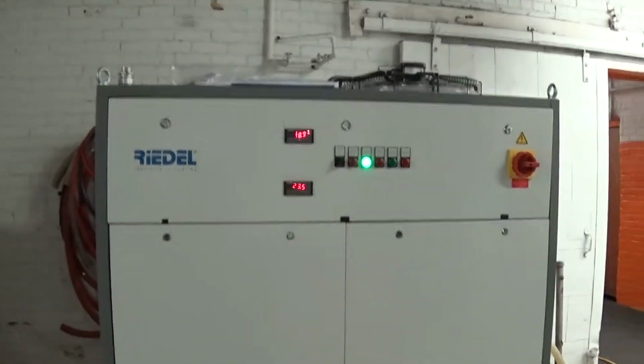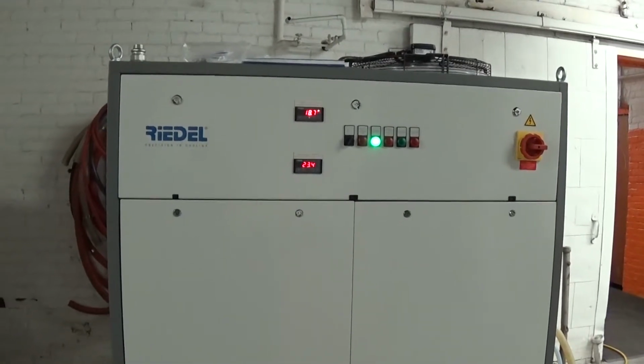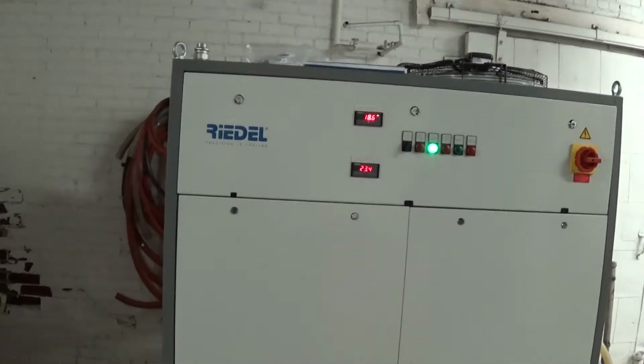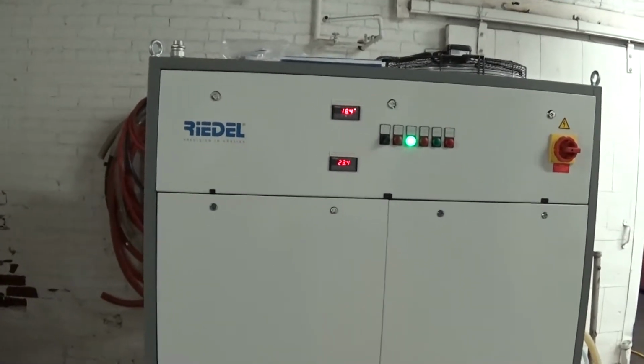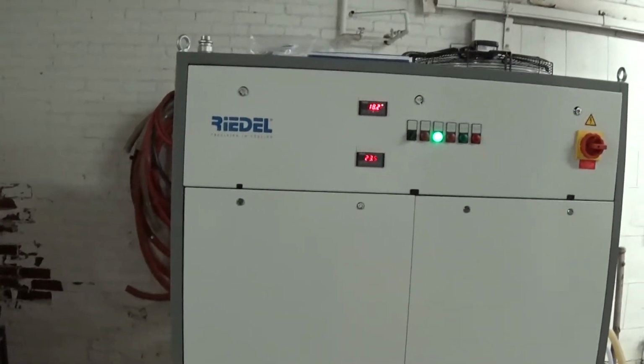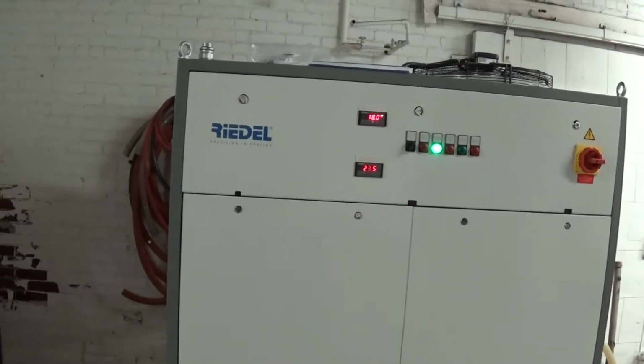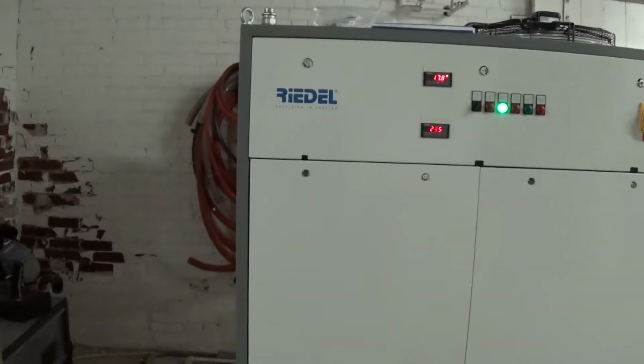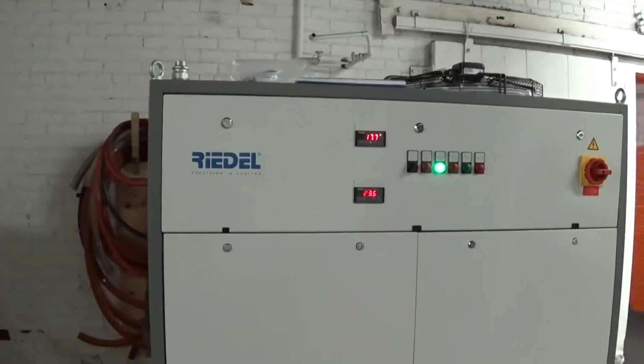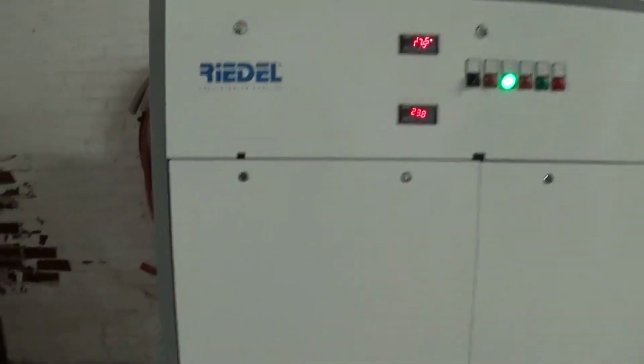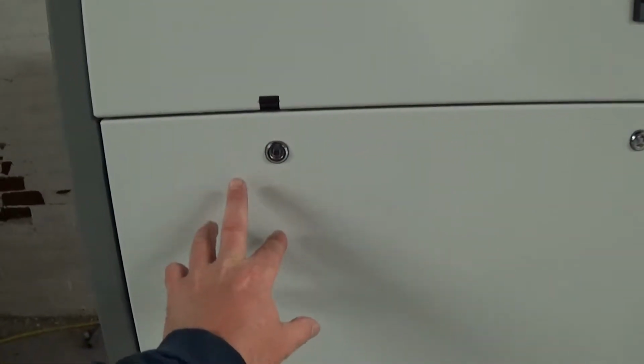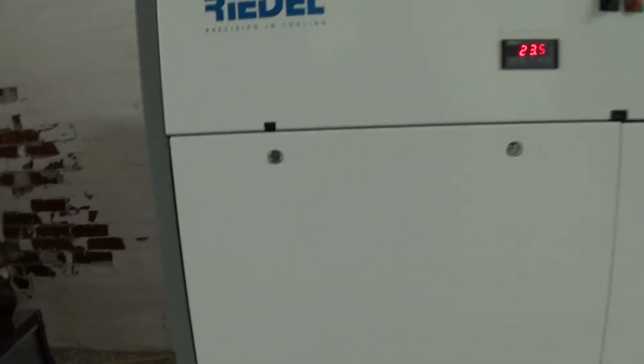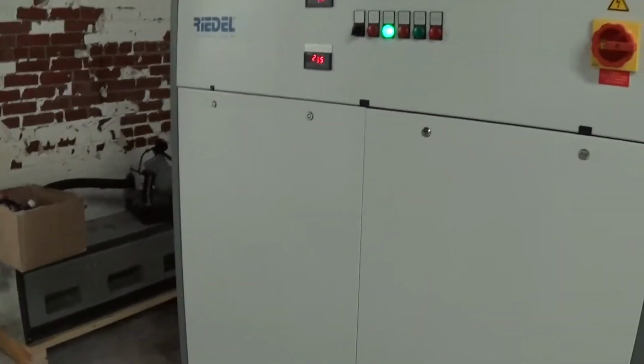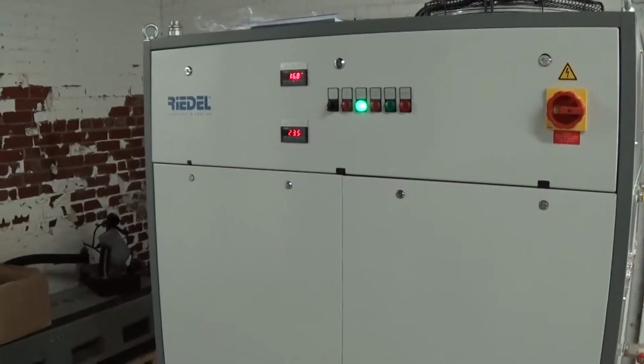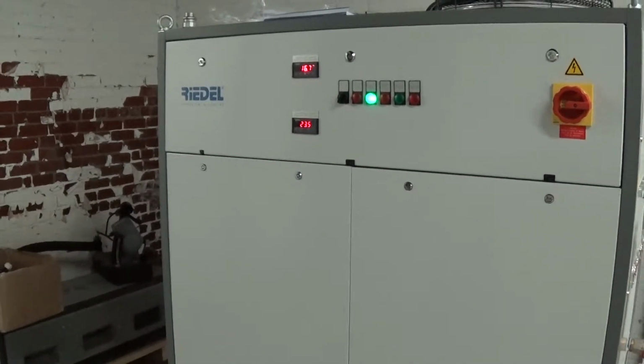With that hot gas bypass, we can actually afford to have that fairly tight window. If you find in the field, even with a healthy load, that the chiller never shuts off, which some people design them that way, they want to leave the compressors running almost all the time and control the cycling with the hot gas bypass capacity control. But if you find that's a problem, or you want the compressors to shut off, that blue hot gas bypass that was located behind this panel, that's one screw. You can simply disconnect that hot gas refrigerant bypass solenoid if you wanted to reach your set point quicker and have the compressors turn off.